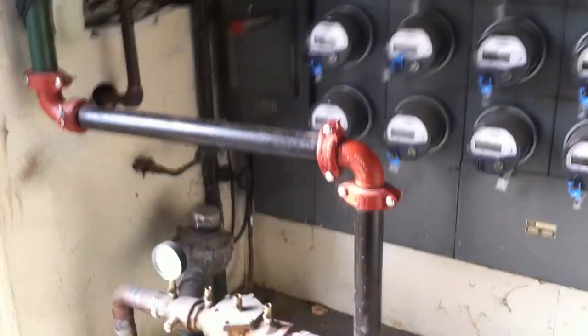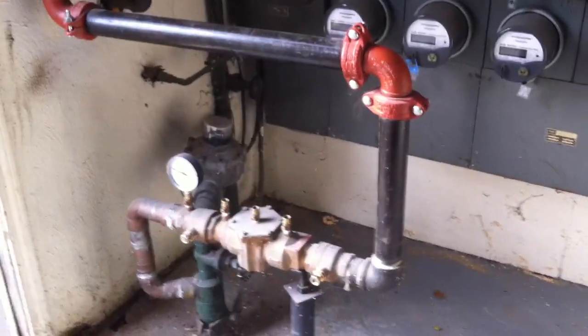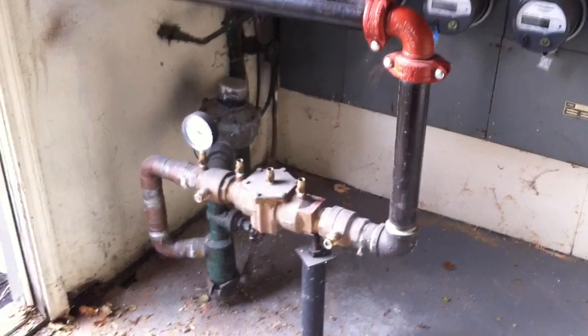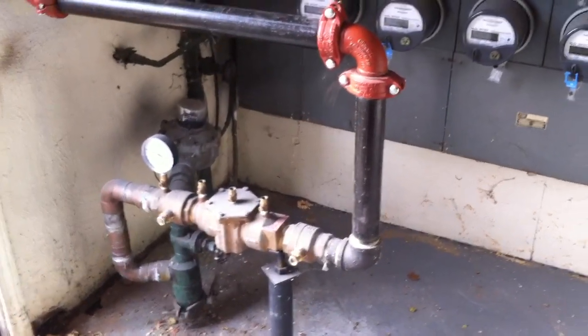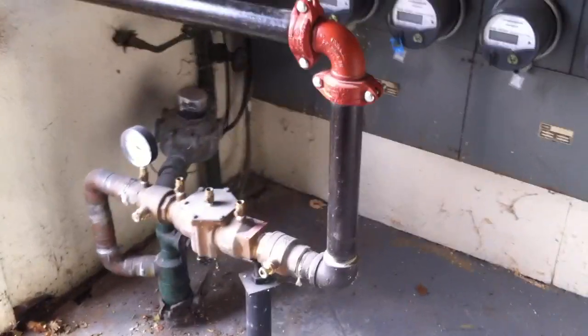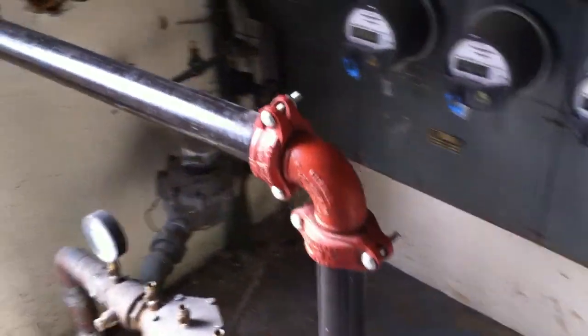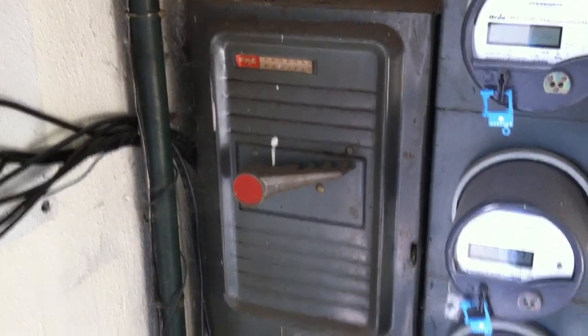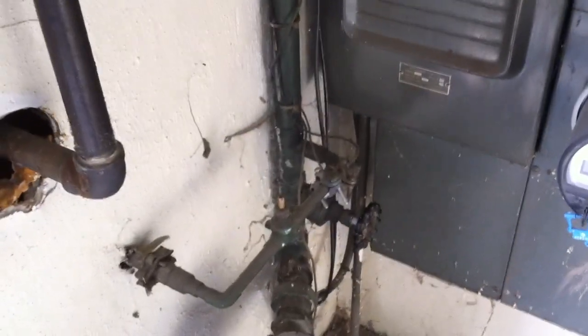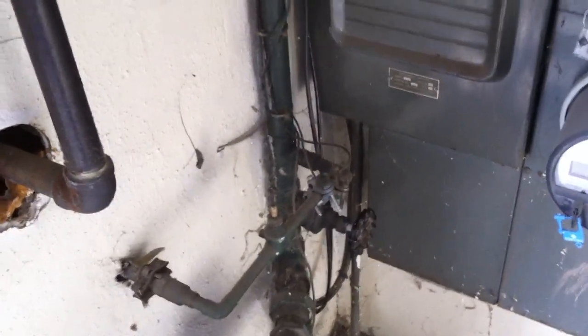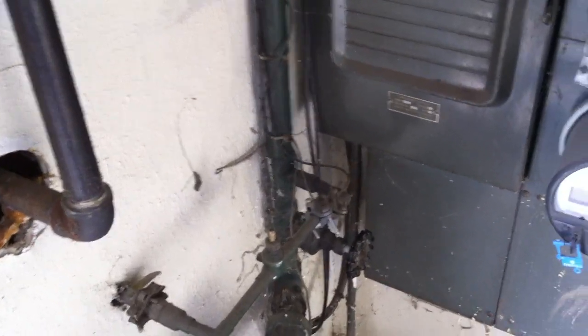Now, this is a great example of a violation of the workspace requirements in section 110.26A. Section A1 requires 3 feet of depth in front of this equipment. And as you can see, we've got this water pipe here, a water meter. I don't even know if you can open that cover.